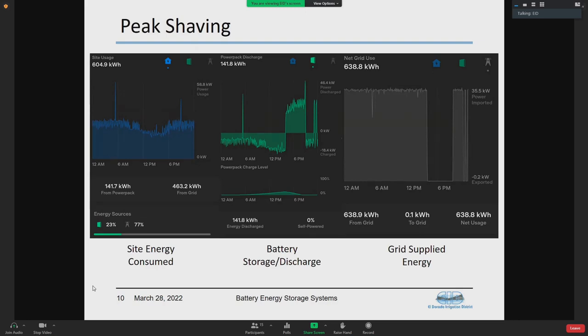That's where we get those demand response charges on our monthly bill. Across in green, you can see what our battery is doing. Anything below that flat line, the battery is charging; anything above it, it's discharging. During off-peak hours, it's charging the battery gradually throughout the day, except where it lines up with our peaks in demand, where it discharges and matches that power to normalize the energy coming into the site.